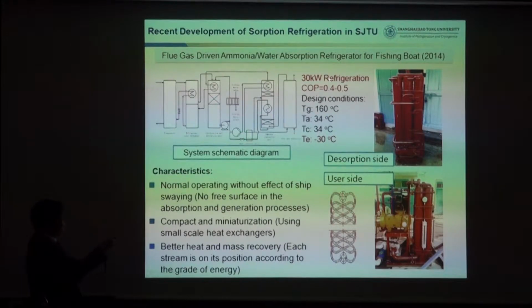So what's the COP? Normally we developed about a 30 kilowatt refrigeration unit, with a generation temperature of 160 degrees centigrade and an evaporation temperature of minus 30 degrees, and you get a COP of 0.4 to 0.5. That's very high for refrigeration purposes. So this is our design machine. Originally we considered it for a waste heat driven absorption refrigerator ice maker for fishing boats. It would be put on the boat, so the fishing boat needn't bring any ice when it goes out for 2 weeks or 1 month, something like that. If it's installed on the boat, it should have an anti-swaying function for the boat.